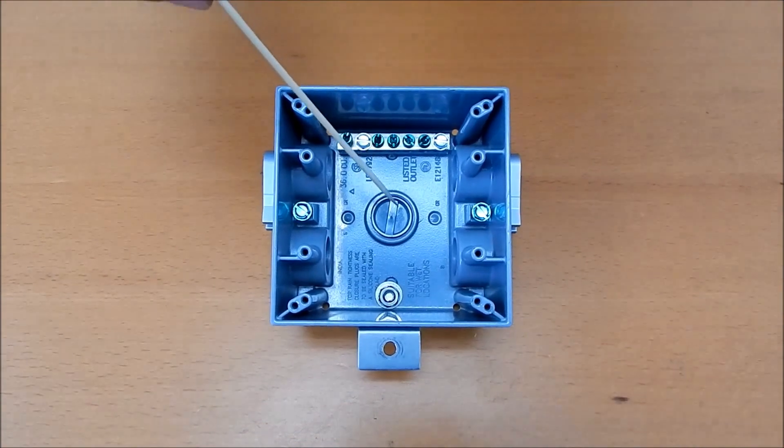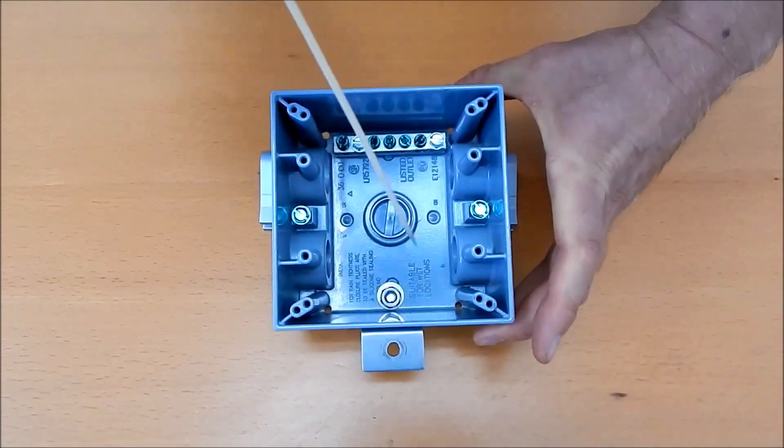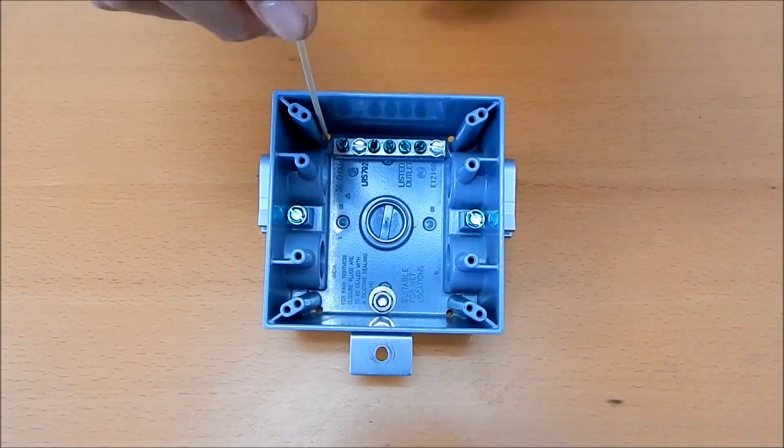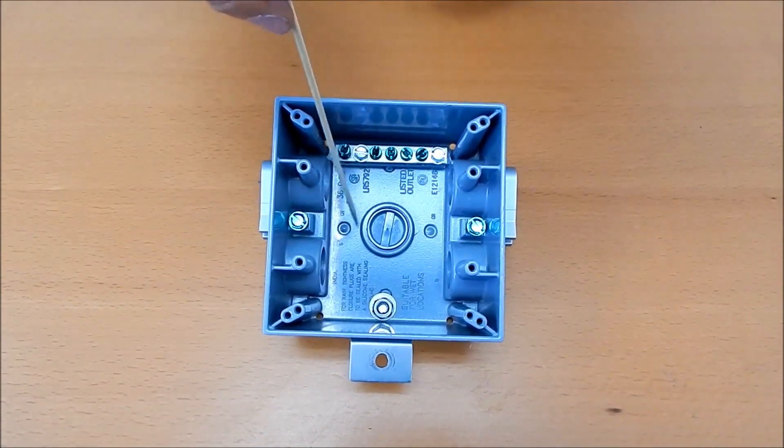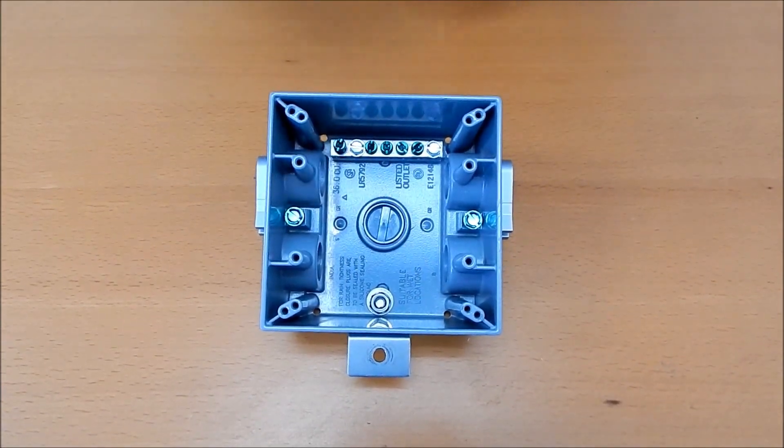One of the other things that we've done to modify the J-Box here is that we've got these holes drilled in the corners. And these are what they call weep holes. What they're designed to do is if there's any water intrusion in the box, you don't want it to stay in there. You want it to escape, and so that's what these holes are designed for.